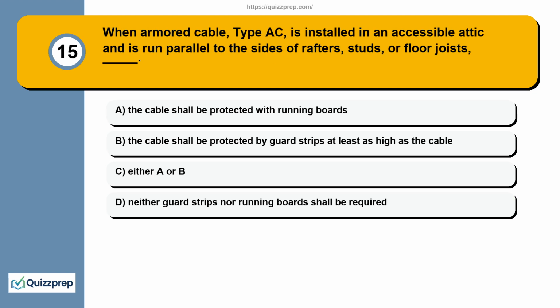Question 15. When armored cable, type AC, is installed in an accessible attic and is run parallel to the sides of rafters, studs, or floor joists, the cable shall be protected with running boards. The cable shall be protected by guard strips at least as high as the cable. Either A or B. Neither guard strips nor running boards shall be required.